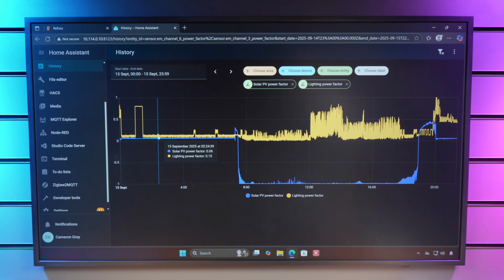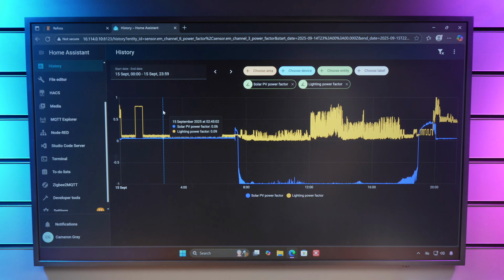Because these power factors are so similar, there isn't really much fluctuation at all. You can see there's a big spike here where the lighting jumps up much higher. This would have been when I turned on the heated mirror in the bathroom, a mirror that heats up to demist it. I must have turned it on as a night light. The heating element is about 30-40 watts and fully resistive, so that will massively increase the power factor. But overnight, when the solar's not generating, the lighting power factor is really quite stable.